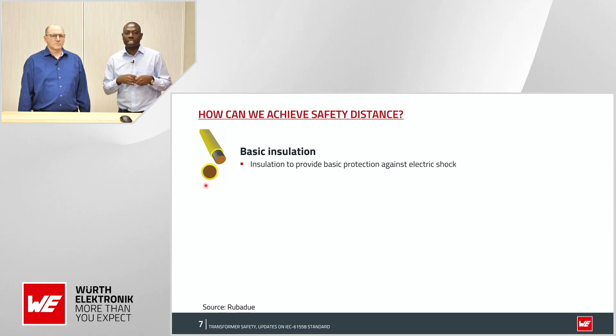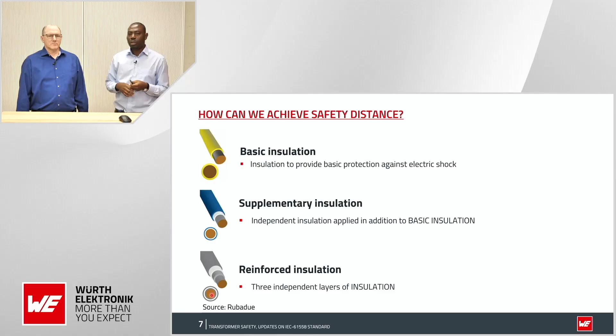For supplementary insulation, you again have the copper, but now with a double layer of insulation—shown in the picture as a white layer and a blue layer. For reinforced insulation, there are three layers: the copper in the middle, then white, then gray, giving three levels of insulation for more safety.